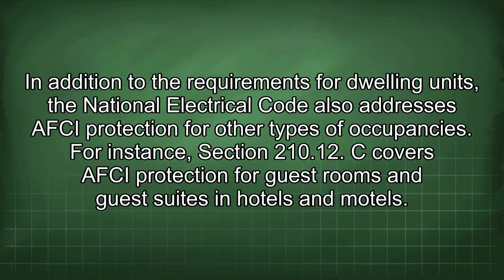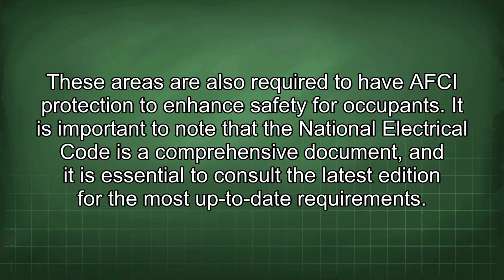In addition to the requirements for dwelling units, the National Electrical Code also addresses AFCI protection for other types of occupancies. For instance, Section 210.12 C covers AFCI protection for guest rooms and guest suites in hotels and motels. These areas are also required to have AFCI protection to enhance safety for occupants. It is important to note that the National Electrical Code is a comprehensive document, and it is essential to consult the latest edition for the most up-to-date requirements.